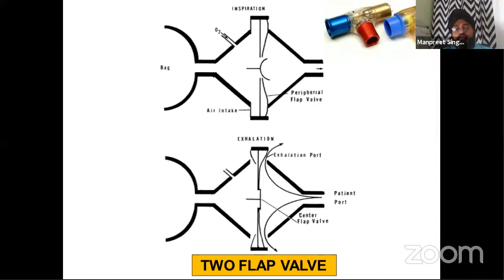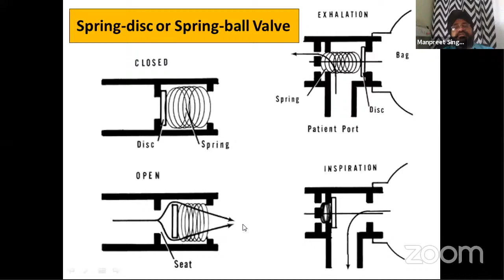Similarly, there is a spring disc valve which has a spring with a disc, and the disc sits in the midline, and whenever there is an inhalation, you can see, follow this arrow, when the air goes in, the disc moves on the spring to the back, and the air goes inside to the patient. And similarly, when the expiration is there, that comes back, and from the sides, the exhalation occurs.